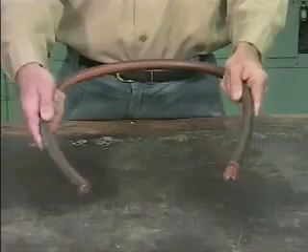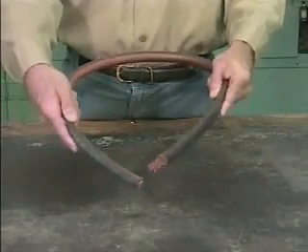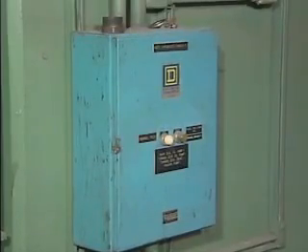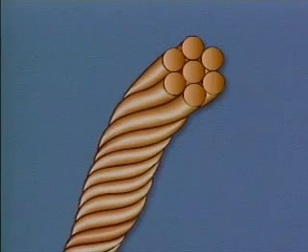Stranded conductors are more flexible and easier to manipulate than solid conductors that are roughly the same size. Stranded conductors are typically used in situations such as conduit installations and control panels, where conductors sometimes need to be bent or bundled. A bare conductor is a length of solid or stranded metal wire with no insulation or cover.